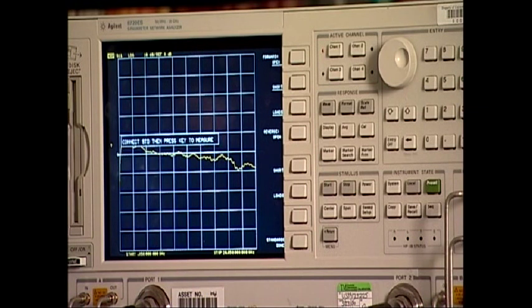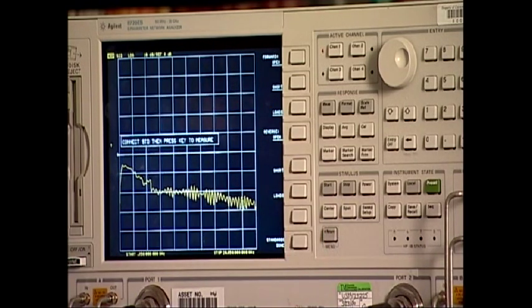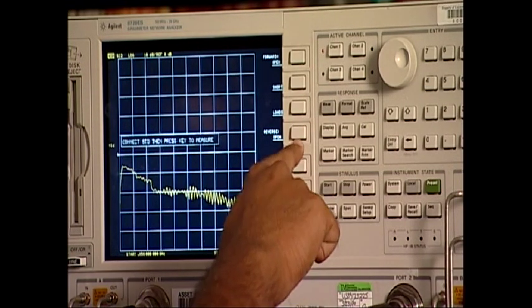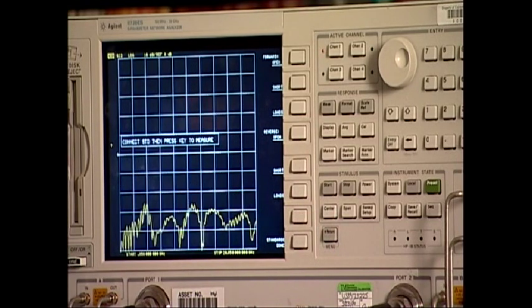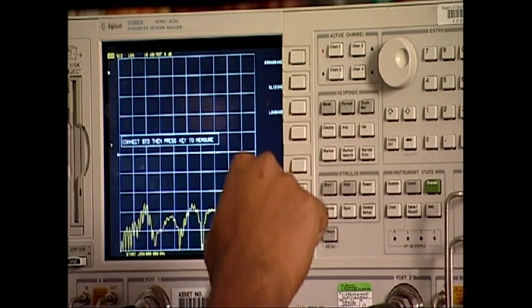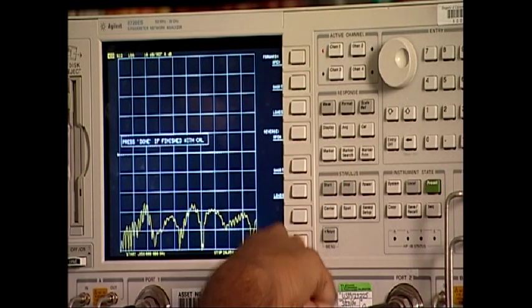Now for the reverse measurements, we connect the cable at port 2 and connect the open standard to our cable and select open. We then connect the short load to the cable at port 2 and select short. We then connect the load standard to port 2, select load, select broadband, done loads.